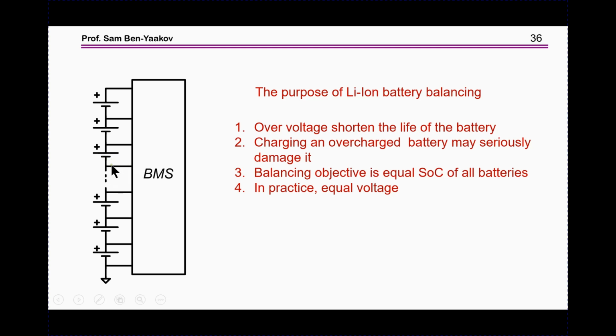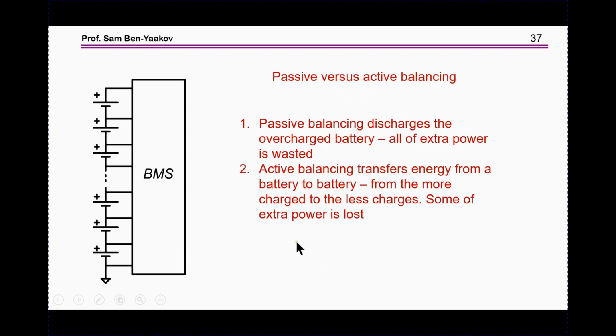You have to make sure that in a string like that, and a lithium ion battery has a voltage between 3 and 4 volts, so to achieve 400 volts you need 100 batteries. Each one is being charged and discharged in series, and you have to make sure that none will be completely or partially discharged while another is fully charged. This is the task of the battery management unit.